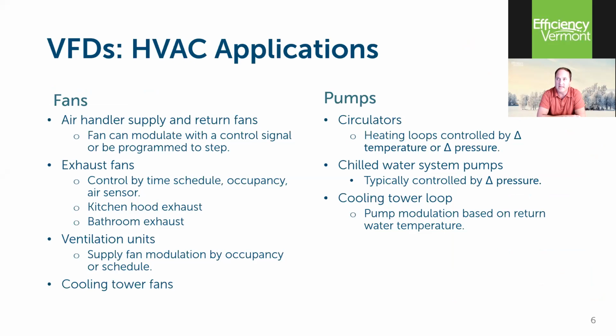Because there are so many data points on these, both in Vermont and nationally, we have an agreement with the Department of Public Service that by horsepower, by VFD application for these 7 applications, we have what's called ascribed savings. So if you have a 10 horse supply fan and you put a VFD on it, it equals X amount of savings, and we can do our project analysis based on that. So this is the target audience for HVAC.